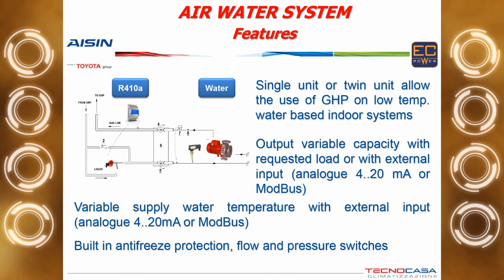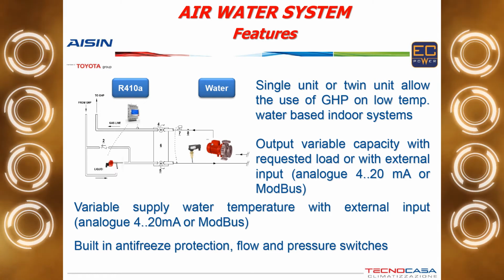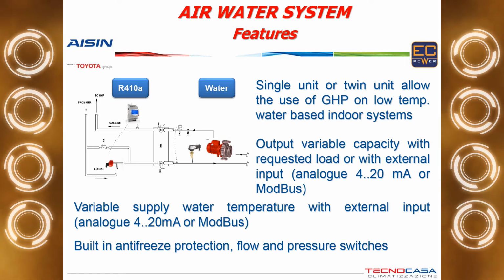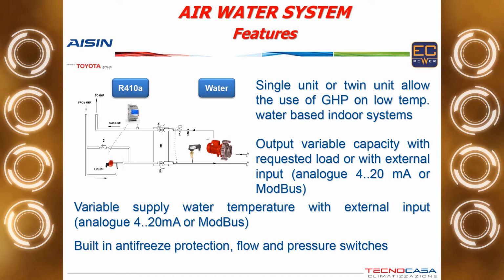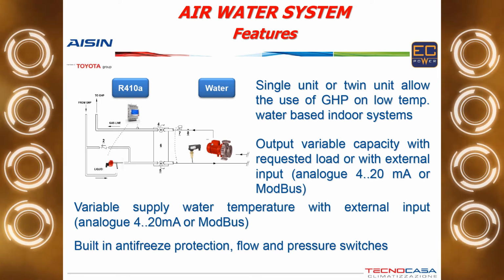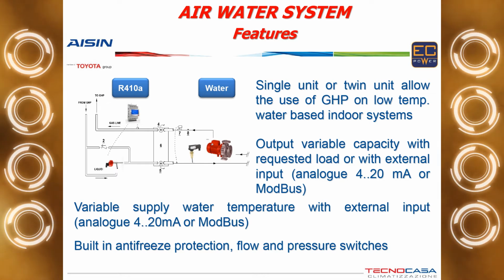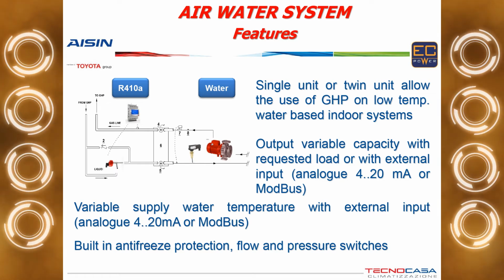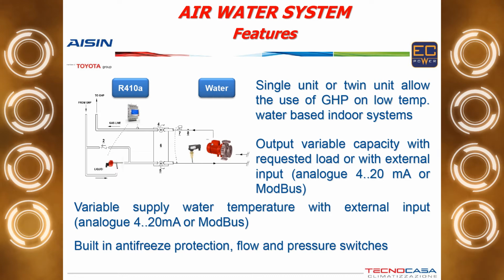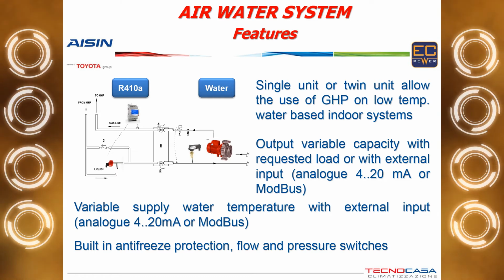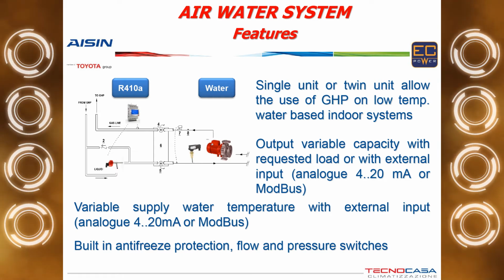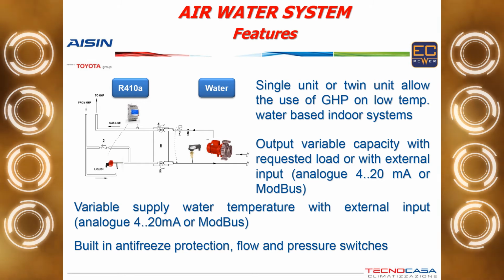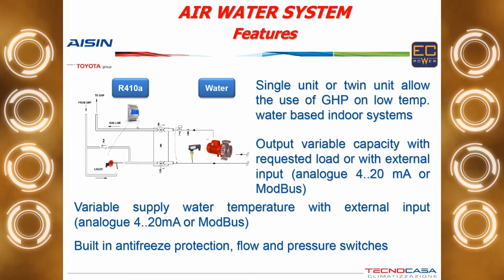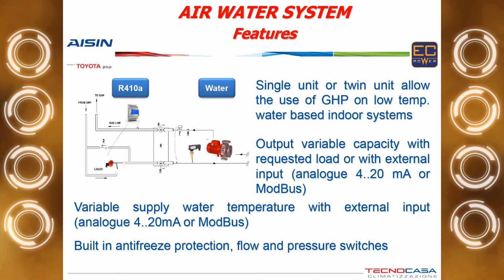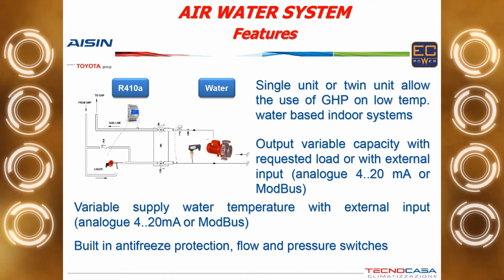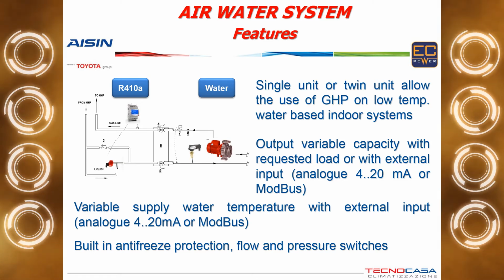when needed. We have a variable capacity output also on the air-to-water system, and we can also send the capacity modulation from an outside signal. So there is a program, of course, embedded in the unit, but if we want, we are fully compatible with the building management system, and so we can accept an input signal to modulate the output as much as the user wants. As well as the supply temperature.